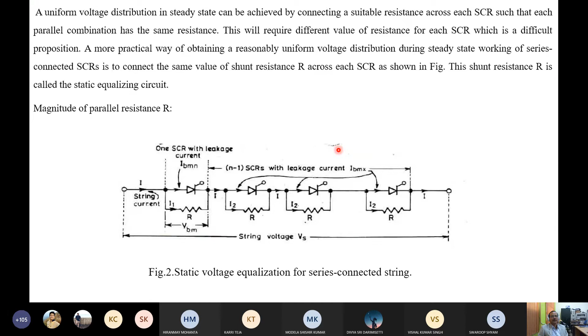We have assumed that all other n minus 1 thyristors have maximum leakage current. Only one thyristor has minimum leakage current, and it will block the maximum voltage. This is the worst condition, and the resistance calculated with this formula and this assumption will give an optimized value of resistance R, which will ensure very minimum voltage differences across the switches.